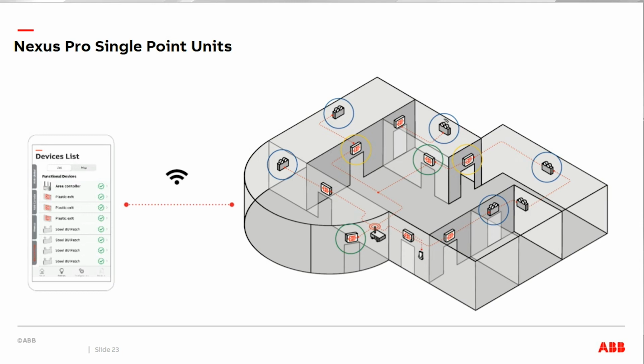The reason we recommend using groups in our Nexus Pro technology is because it allows the units to not all be tested at the same time. So if that eventuality happens and there's a disastrous situation right after your full discharge test, your 90-minute runtime test, you'll at least have some fixtures online and at full capacity, ready to illuminate that path of egress for customers. That's something we have available on our system, and we've highlighted it here by circling the units in different colors.